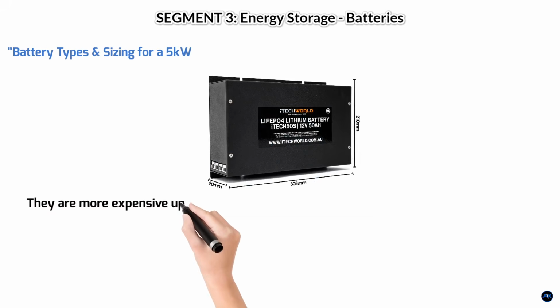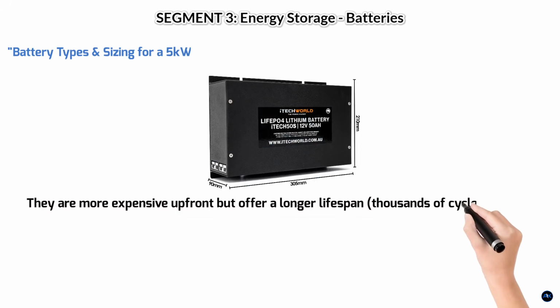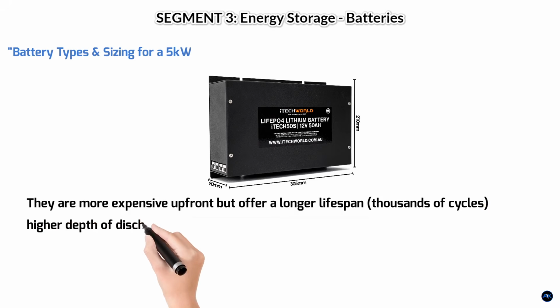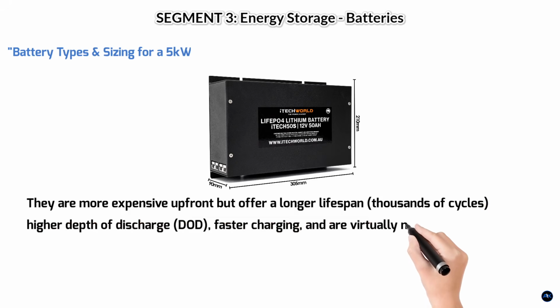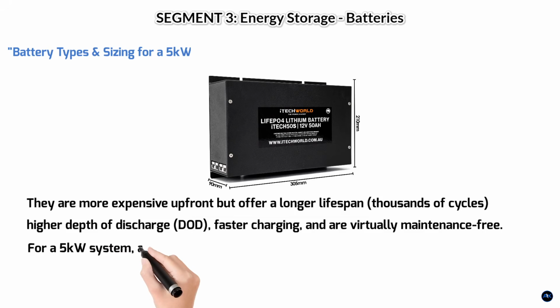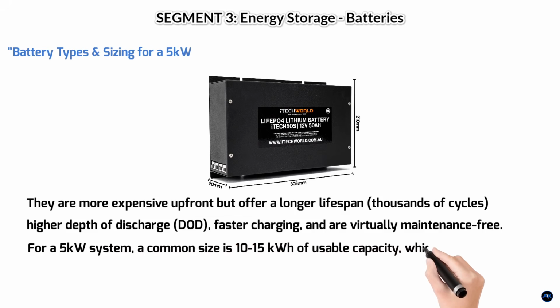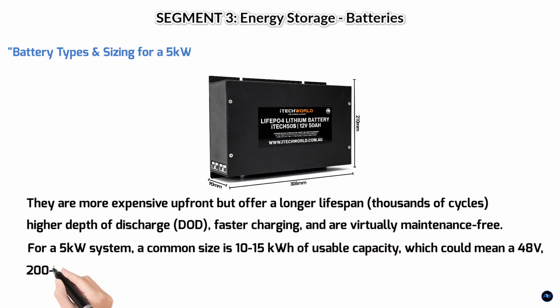They are more expensive upfront but offer a longer lifespan, thousands of cycles, higher depth of discharge (DOD), faster charging, and are virtually maintenance-free. For a 5 kilowatt system, a common size is 10 to 15 kilowatt hours of usable capacity, which could mean a 48 volt, 200 to 300 amp hour battery bank.